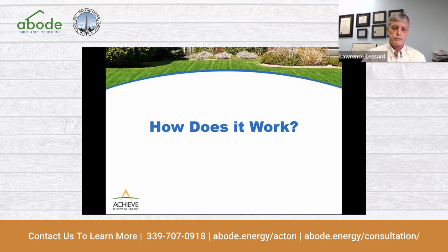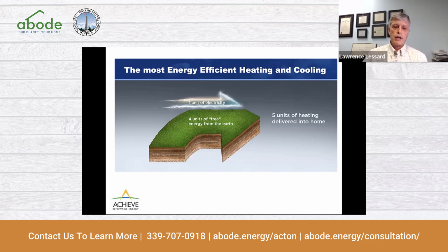So how does it work? How does a ground source heat pump actually provide heating to a house? We use electricity to power refrigeration equipment within the heat pump. That's a compressor and some valves and controls that move refrigerant around and evaporate it in one place and condense it in another. That process is the same as the way your refrigerator works, so it's not like it's magical. And if you use 1 unit of electricity, let's say a kilowatt of electricity with a geothermal system, that is not used to make heat for the house, it's used to harvest it from the ground.